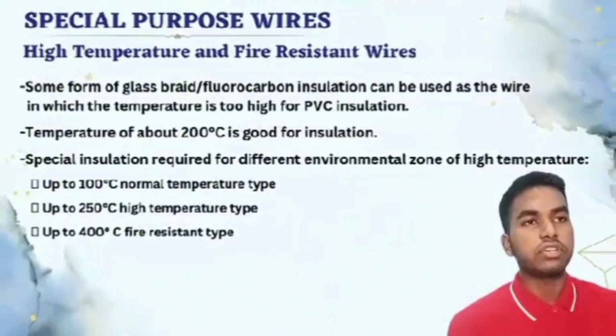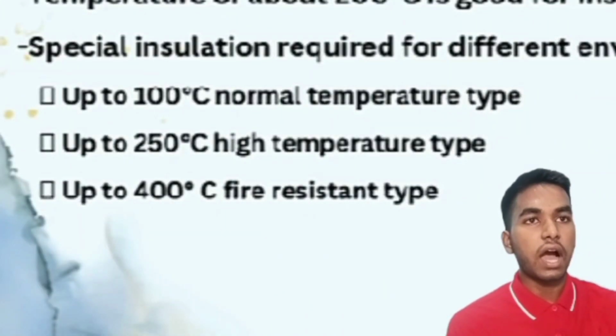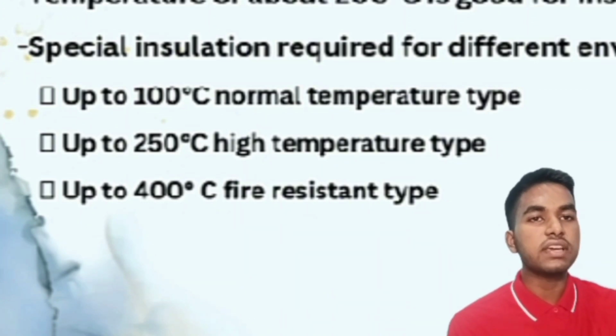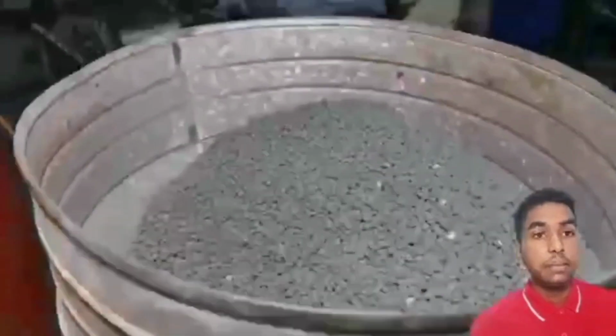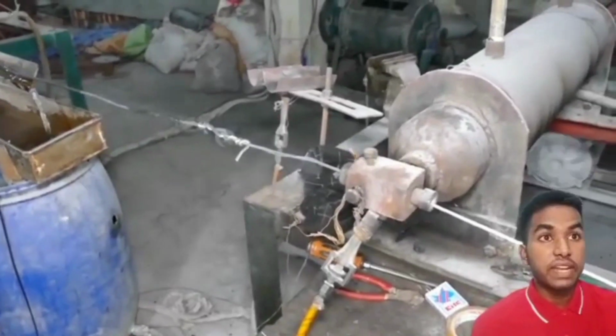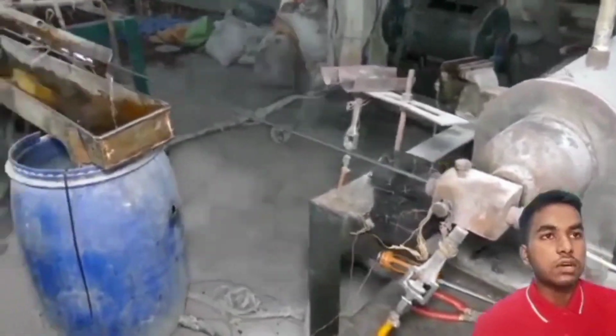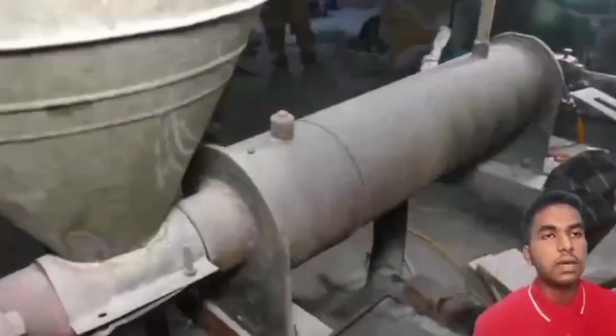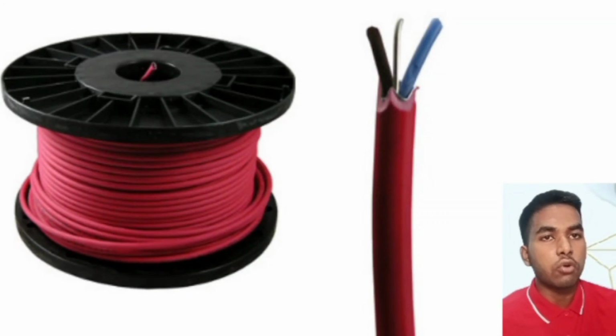of high temperature. The first one is up to 100 degrees Celsius, normal temperature type. The next one is up to 250 degrees Celsius, high temperature type. Then the last is up to 400 degrees Celsius, fire resistant type. The temperature range is up to 400 degrees Celsius and fire resistant for 5 minutes against a temperature of 1100 degrees Celsius. The outside insulation color is normally red, sometimes also white.